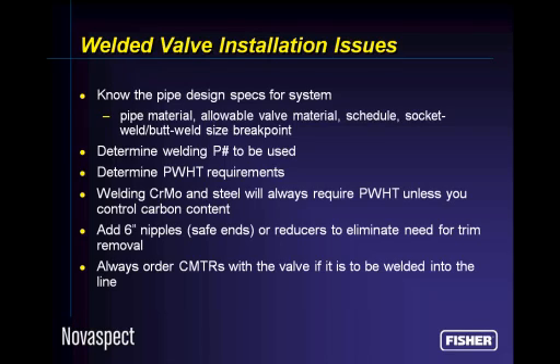And always order chemical and mechanical test reports with your valve if your valve is to be welded into the line. You're going to need that to support your determination of the weld rod and the weld process. Your certified welders need to see the CMTRs before they should feel confident that they're using the right weld materials to put the valve in line.